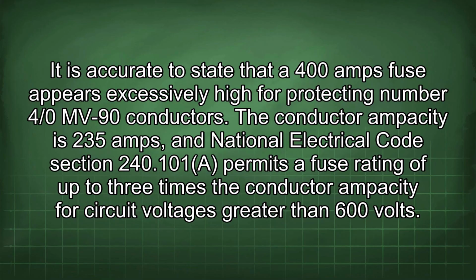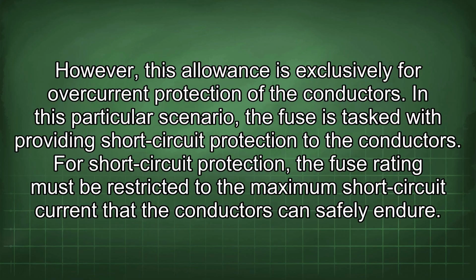It is accurate to state that a 400 amps fuse appears excessively high for protecting number 4/0 MV-90 conductors. The conductor ampacity is 235 amps, and National Electrical Code Section 240.101 permits a fuse rating of up to 3 times the conductor ampacity for circuit voltages greater than 600 volts. However, this allowance is exclusively for overcurrent protection of the conductors.